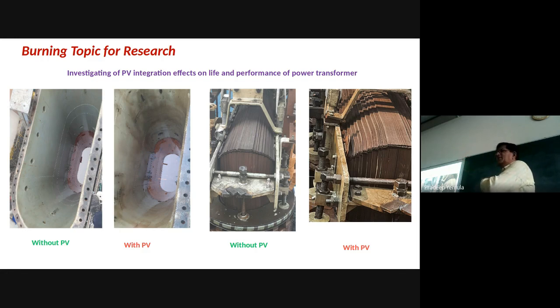Opening a transformer and lifting the core for inspection is a rare thing. Generally nobody does it. If you go to Transco or Discom, they will never open a transformer for overhauling - run, fail, use and throw, go for new. But we don't do that. It's a natural resource, we should not waste anything. We are trying to find out the reason, because in the scientific department they will not accept otherwise - we have to do it like this.